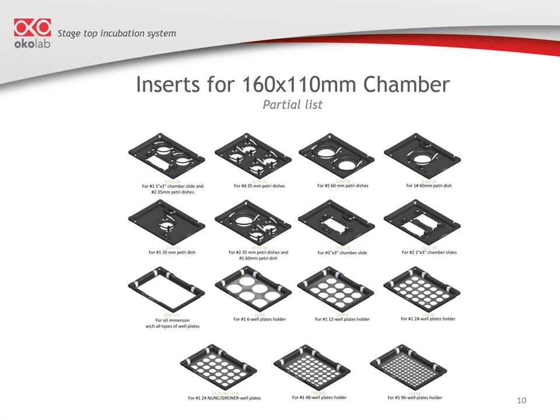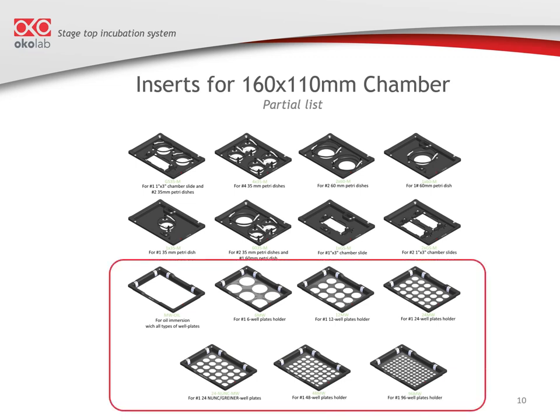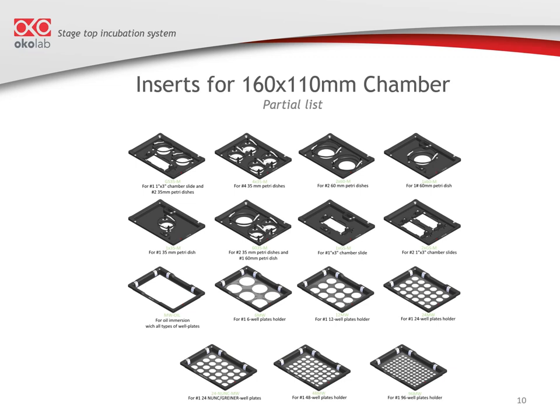This slide shows a partial list of sample inserts. Please focus on the inserts in the red box — these are meant for multi-well plates. A stage top incubator will require a perforated metal plate to improve thermal uniformity on the bottom surface. However, if you are using an oil immersion objective, the insert for multi-well plates will be an open frame, as shown in the blue box, to allow the objective to move freely between wells.